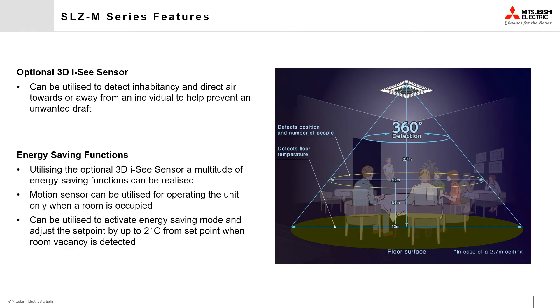The optional 3D i-See sensor can be used to detect the number of people in the room and set the air conditioning power level accordingly. This works by adjusting the set point by one or two degrees, reducing the load on the unit when lower or no occupancy is detected.